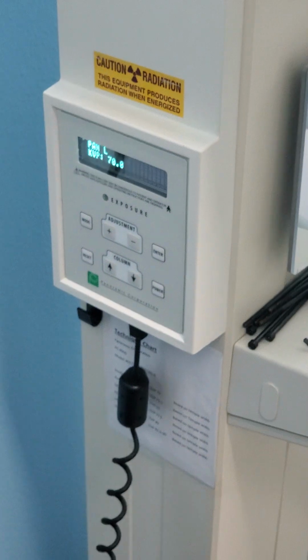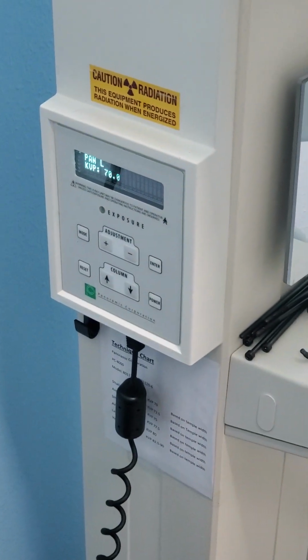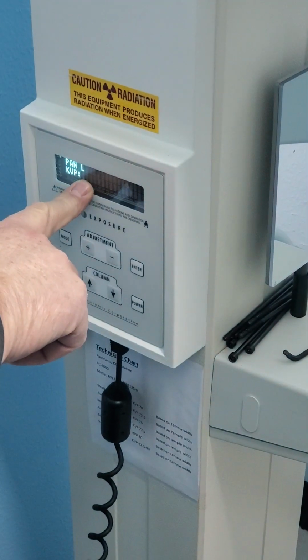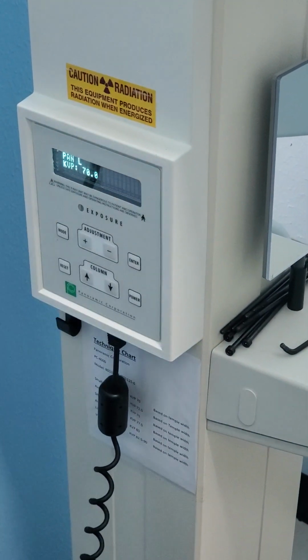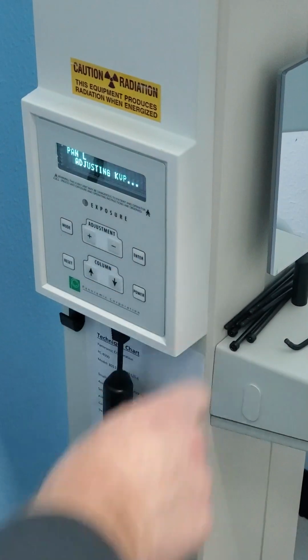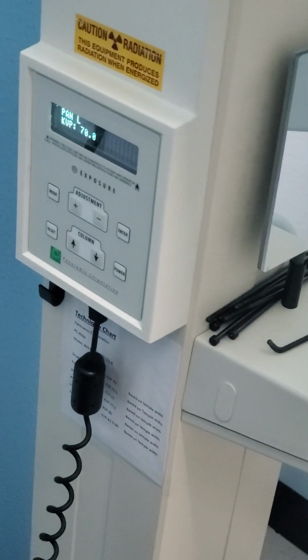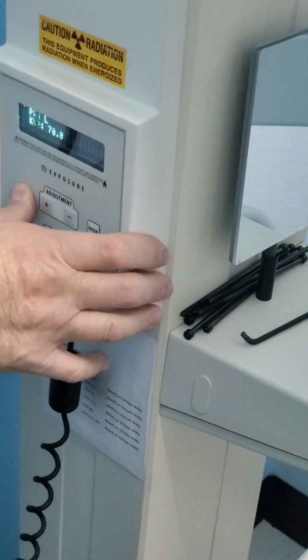Press mode - there's KVP, it's defaulting to 70, which is what we want. It's a flashing data point, so whenever there's a flashing data point we have to enter it. We'll hear the variac move - it moves to 70 and stops. Push mode again - ready to expose.